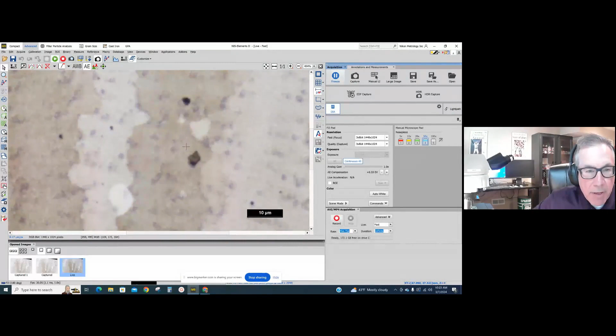So as far as capturing, I've got an image, I want to focus. I can zoom in with my mouse wheel. I'm just rolling my mouse wheel forward, so that I can adjust the focus on the microscope that way. I can also use this very popular magnifying glass up in the top left corner, so I can magnify some part of the image and focus on something in a magnified view while I'm still seeing the rest of the image in full mode. There's also at the bottom of our software this black progress bar. As I move out of focus, the black bar moves to the left. As I come into focus, it moves to the right. And when it's maximized, that's electronically saying that's our best focus.